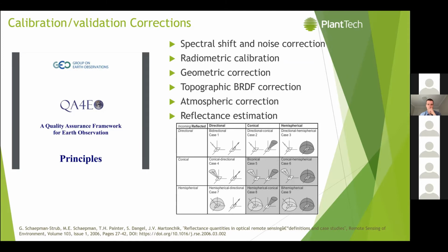This spectrophotometer that we have been using is manufactured by Specim. They do radiometric calibration every year. As we don't have any lab facilities to check radiometric calibration, we are not doing any lab work. We are only checking, calibrating, and validating in field conditions.